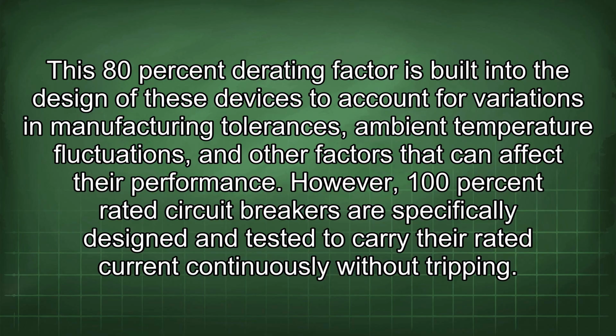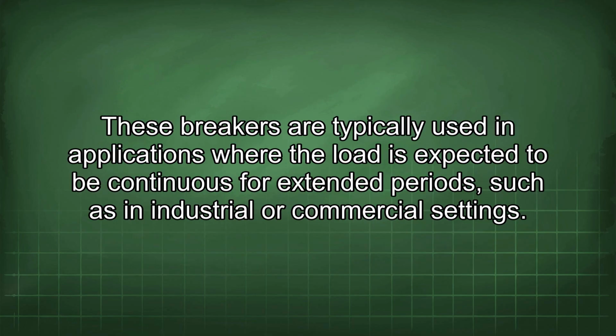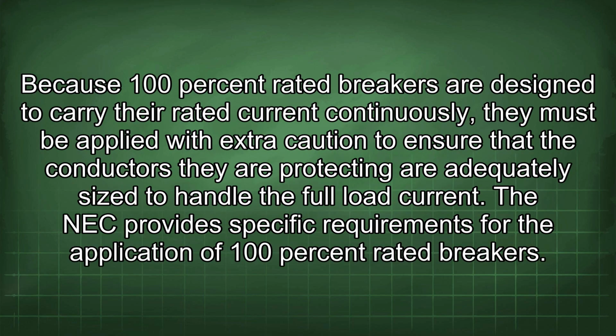However, 100% rated circuit breakers are specifically designed and tested to carry their rated current continuously without tripping. These breakers are typically used in applications where the load is expected to be continuous for extended periods, such as in industrial or commercial settings. Because 100% rated breakers are designed to carry their rated current continuously, they must be applied with extra caution to ensure that the conductors they are protecting are adequately sized to handle the full load current.